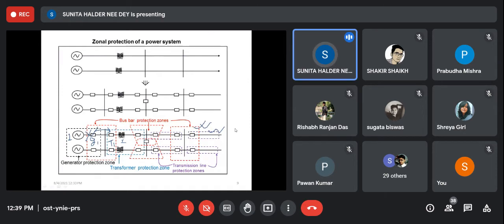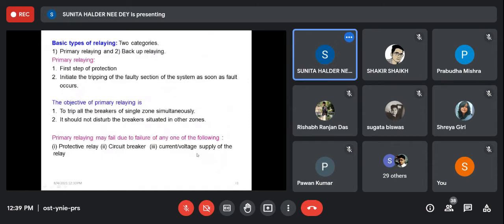That's why there is no hard and fast rule for that. So whatever I have told, the relay can be categorized into two types. One is basic relaying or primary relaying, or the backup relaying. So primary relaying always gives the first step of protection or primary importance to the protection. By any means, if it fails, then backup relay will give the secondary protection. That means primary relaying always disconnects the smallest unhealthy zone, and backup relaying always disconnects a higher, larger region than the primary relaying is disconnecting.